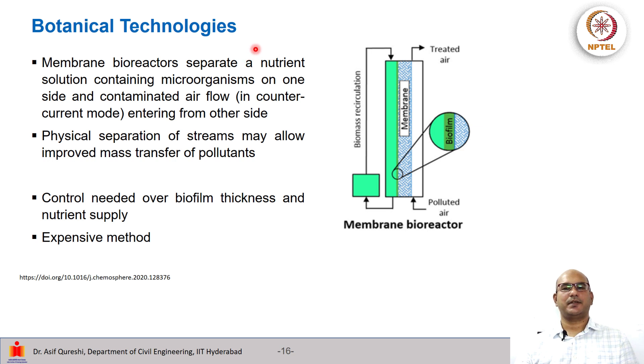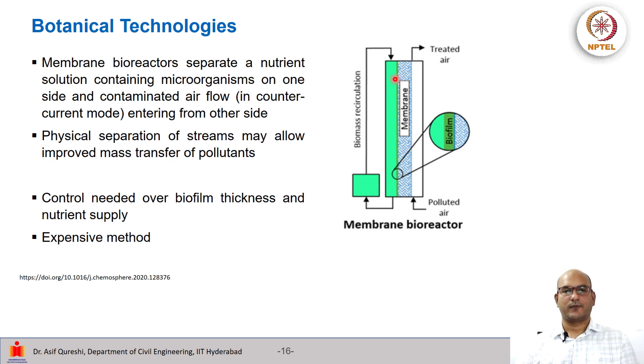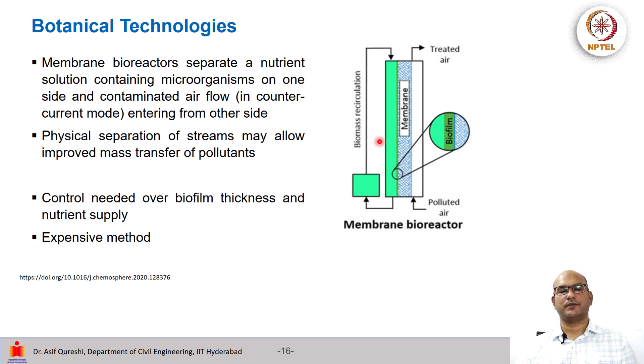Then we have botanical-based technologies such as membrane bioreactors. Here polluted air flows upward. There is a membrane with a biofilm on the other side, and recirculation of biomass is happening. These membrane bioreactors separate a nutrient solution containing microorganisms on one side — shown in green — and contaminated air flows in a counter-current mode on the other side. This physical separation of streams may allow for improved mass transfer of pollutant from air to the solution, and the biofilm aids in degradation. However, controlling the biofilm and nutrient supply is required, and it is an expensive method.